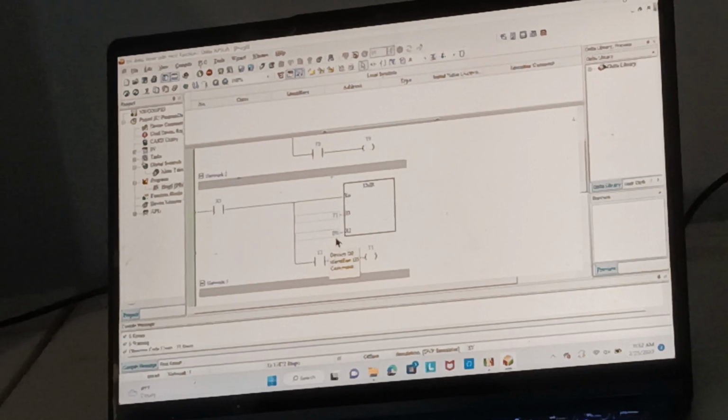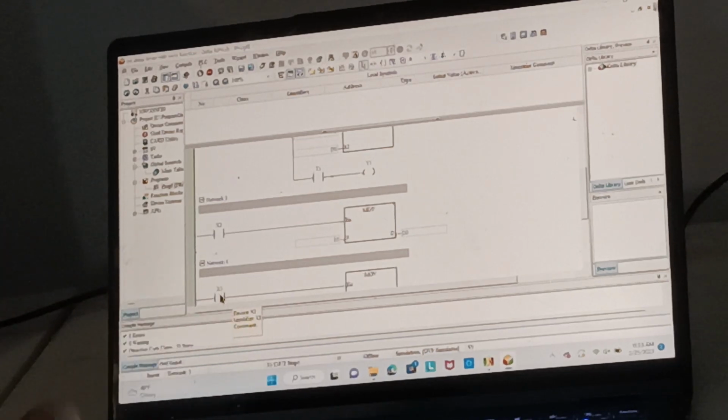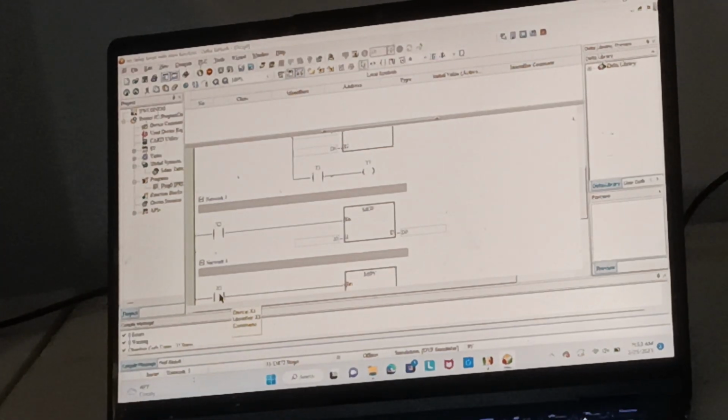Basically, that is a placeholder so that you can do inputs for functions that set this D0 to 20/10 of a second, or 2 seconds. This move function sets data register D0 to 2 seconds. Now these inputs would be like push buttons that an operator sets. Maybe they want to increase the on delay or decrease or whatever.